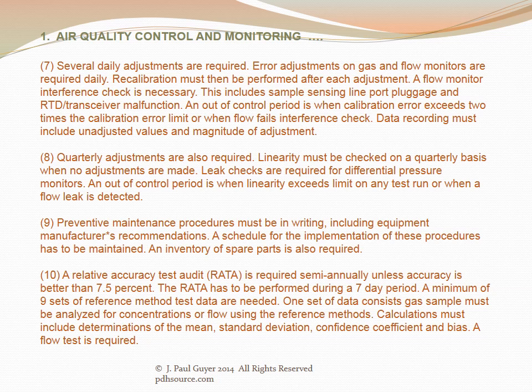Preventive maintenance procedures must be in writing, including equipment manufacturer's recommendations, with a schedule for implementation maintained and an inventory of spare parts required. A relative accuracy test audit is required semi-annually unless accuracy is better than 7.5 percent. The RATA has to be performed during a seven-day period, with a minimum of nine sets of reference method test data. One set of data consists of a gas sample analyzed for concentrations or flow using the reference method. Calculations must include determinations of the mean, standard deviation, confidence coefficient, and bias.